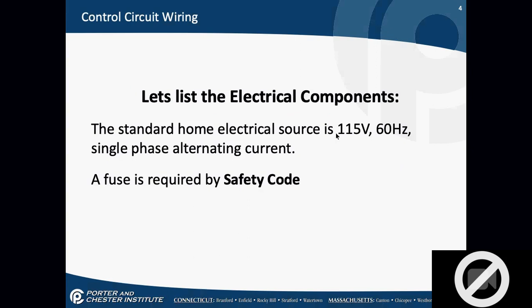Okay, so let's talk about the electrical components. Our standard home electrical source is, the book and everything will say 115 because it's a little bit old, but the reality is most of our voltages now are 120. So 115, 120, it's still standard household electrical code. I have to have a fuse or a breaker. Every circuit I have has to be controlled by a fuse or breaker. It's a protection device. It makes sure that we have proper amperages, we don't have a short, and we're not going to burn the building down.